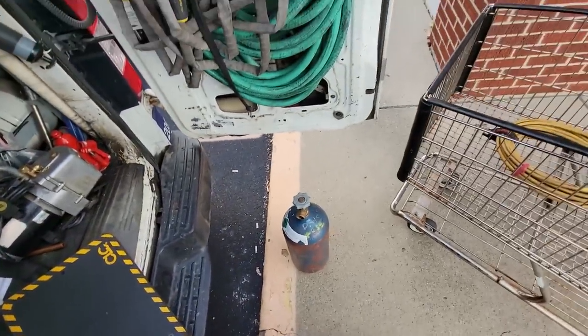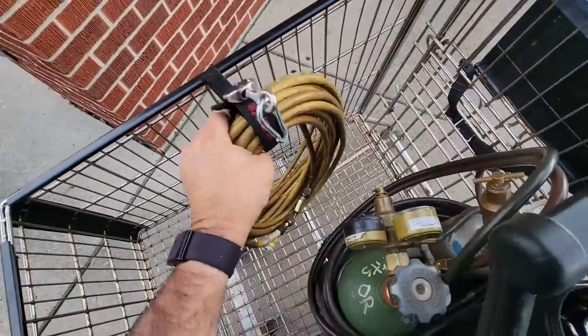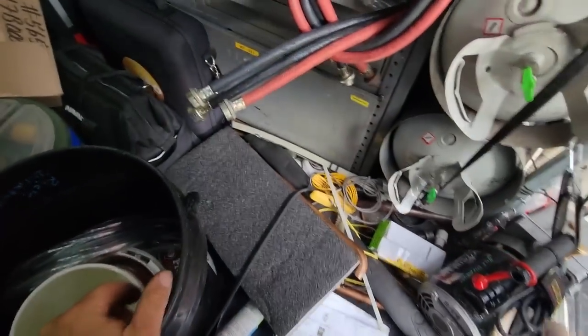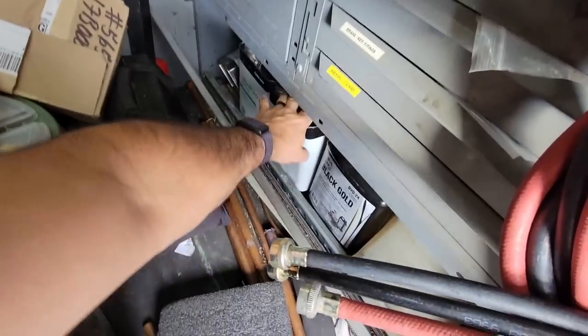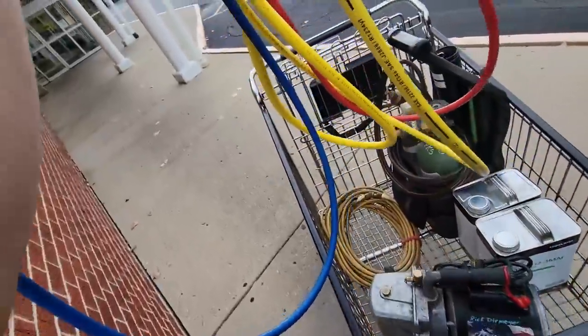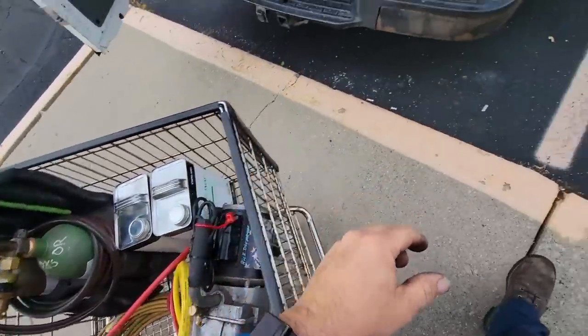So talk to the manager, go and get a little kitty litter. We'll use that to get rid of the oil, which he's going to just take that out of inventory. So we got that there waiting for us. Gotta get some oil, which gotta take every bit of that. Definitely gotta watch oxygen levels in the room. The fan is on. I feel lightheaded already. So we gotta watch that. You don't wanna deplete your oxygen to the point where it ends up making you sick or dead.